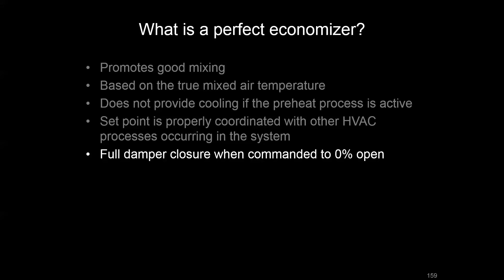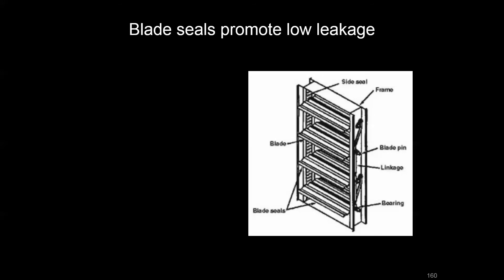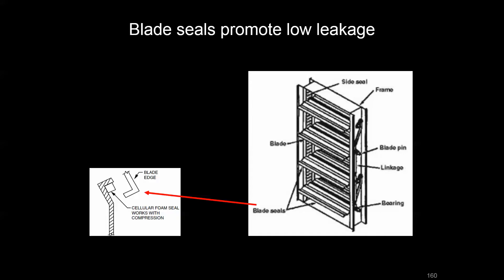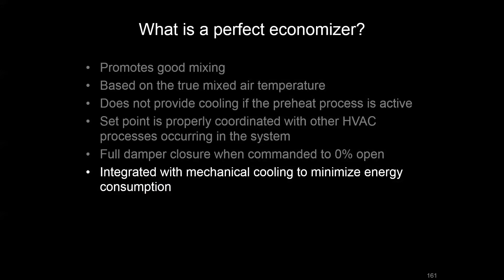When we tell the dampers to close, we should mean it. When the return air damper goes to zero percent open, we don't want any return air bleeding in and heating our air stream. When we tell the outside air damper to close during unoccupied periods, we should expect that it does. One thing that facilitates this is blade seals at the edge of the damper assembly — good foam seals that compress as the damper blades close.